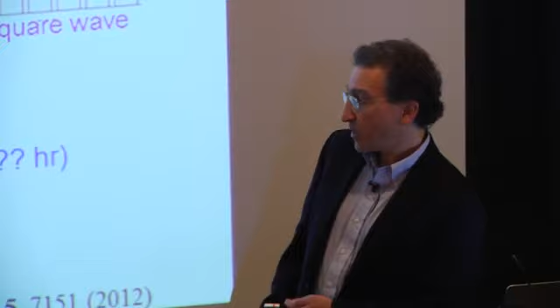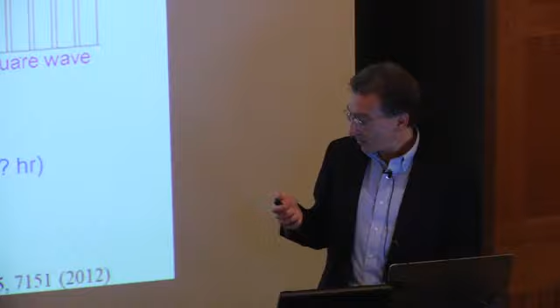So the question is, say you have a 1 megawatt nameplate solar farm. How many megawatts peak power capacity do I need in my battery? How many megawatt hours energy storage do I need in order to turn this into this, or this, or this? And the ratio—what is that? The energy to power ratio is the number of hours you can discharge your battery at full power before it's drained, and that's very different for different applications, and very large for these applications, as we will see.